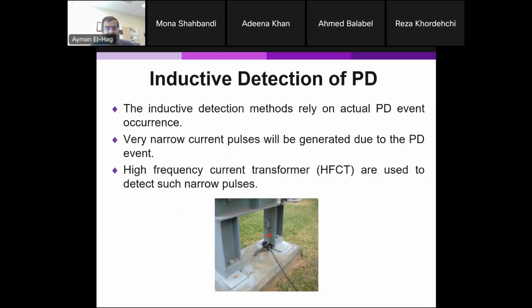Now, the current transformer here has to be designed for this. It has to be a high frequency current transformer, not a regular current transformer, because a regular current transformer can measure frequencies only up to about 300 hertz. After that, the material saturates. The classical ferromagnetic material can only measure currents or voltages in that small frequency range, but after that it cannot. And why can it not? In a very simple way, if you look at the microscopic structure of these ferromagnetic materials, they are made from domains. These are some domains randomly distributed.